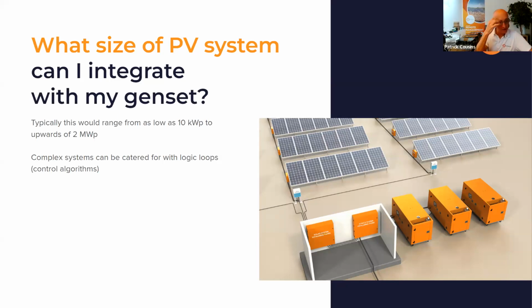But I do need to note here that we do not do phase synchronization. So if there is a whole bank of multiple generators in a larger system, it's still necessary to have a generator synchronization controller, because our way of controlling is more like a SCADA. It's once per second and not in the millisecond area in order to assimilate phases. So that's maybe also something to consider. We would then, in that case, usually communicate with the generator controller system. Yeah, true, Patrick.